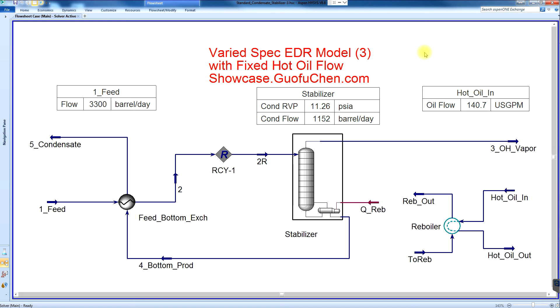The first model is set up in a way that every time it runs, it requires a new different size of heat exchanger, and it will never lead you to a standard plant. On the contrary, the second and third models solve with fixed heat exchanger geometry. After you build the second and third model, now you can declare you have a standard plant.